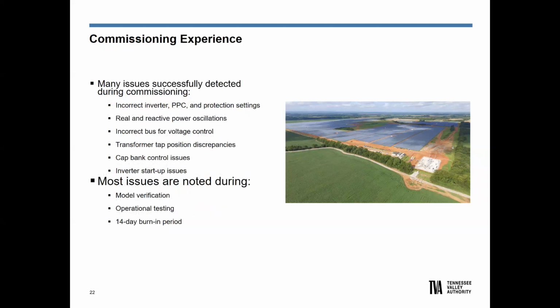With the commissioning experience, many of our issues we detected during commissioning. Incorrect inverter and power plant controller protection settings, things we've heard before here already. We've also seen real and reactive power oscillations. We've seen the wrong buses used for voltage control. Transformer tap position discrepancies are also occurring. We recommend one tap, they land on another, and then they can't figure out why they can't hold voltage. Localized cap bank control issues to offset the reactive penalties there.